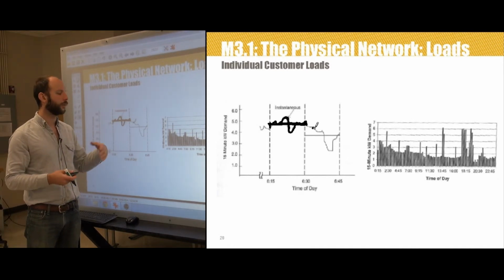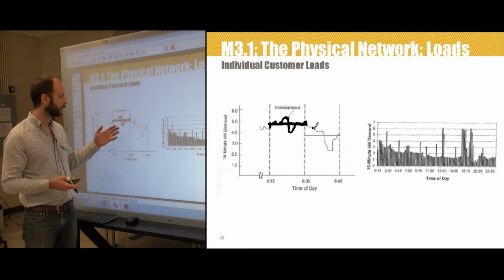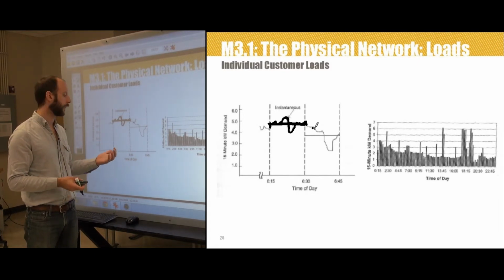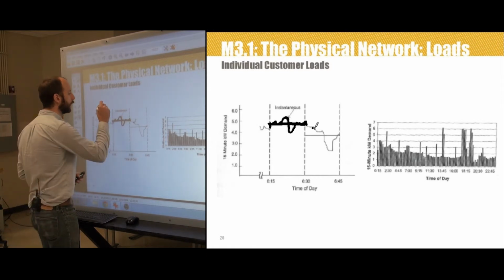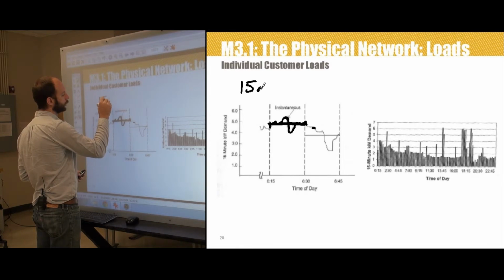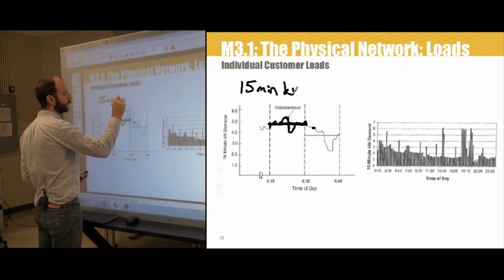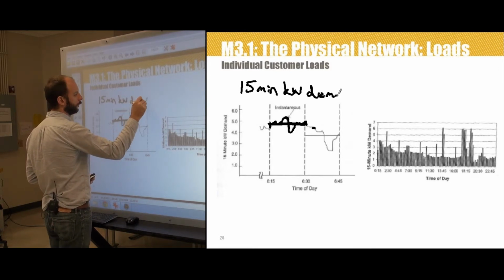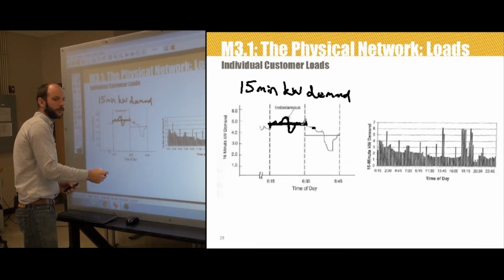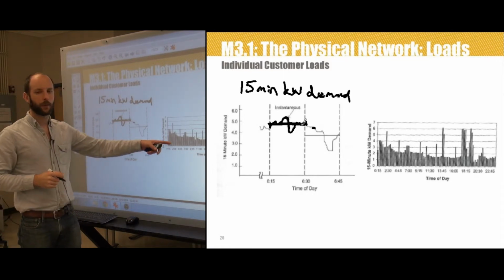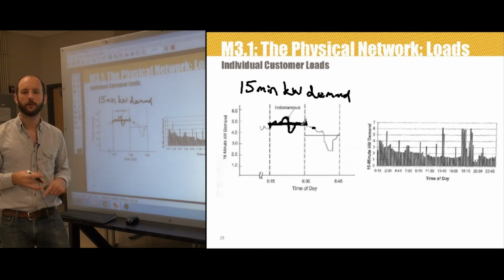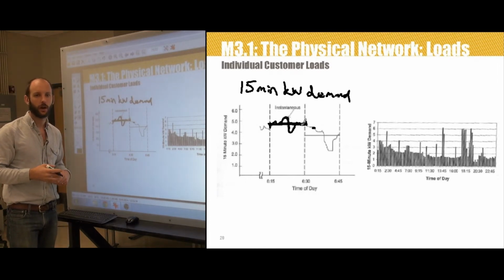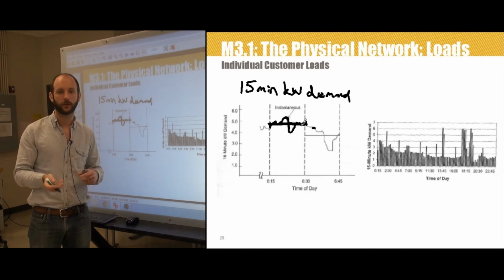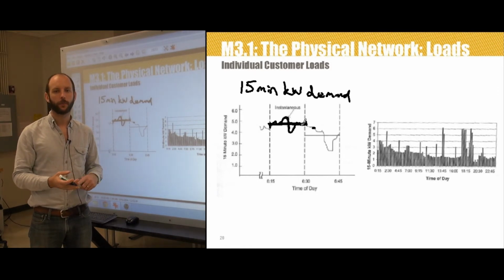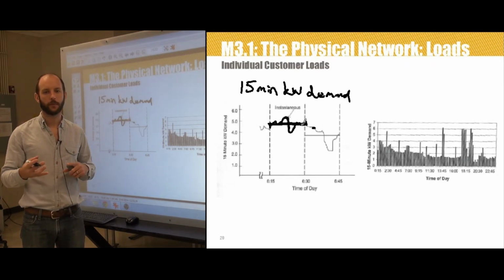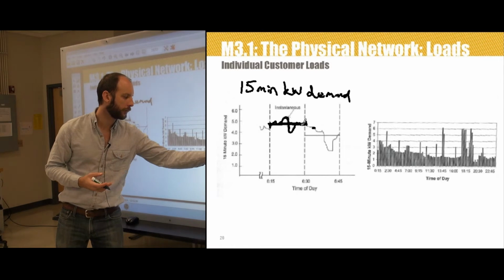But when utilities are doing load studies, typically they use this 15-minute windowing. It's called the 15-minute kilowatt demand. It's kind of got its own name, 15-min kilowatt demand. Right, and that's that 15-minute window from 6:15 to 6:30, for example. So this plot that we have here shows 24 hours of 15-minute kilowatt demand information. And this really actually does represent a typical residential customer. So each of these bars represents 15 minutes of kilowatt demand data during 15-minute intervals over the course of the day, right?